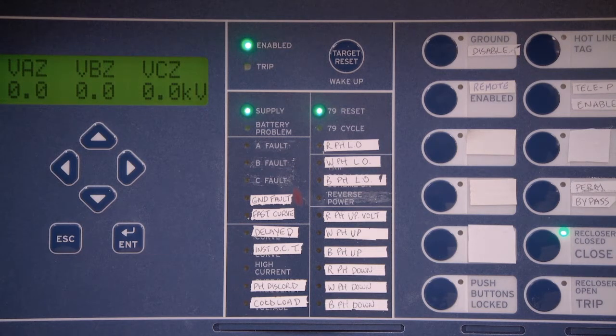When first picking up on a cold load situation, such as a line being out for more than 15 minutes, you will have an increased current surge due to a loss of load diversity. This LED will show you that cold load pickup is active for the programmed cold load duration.